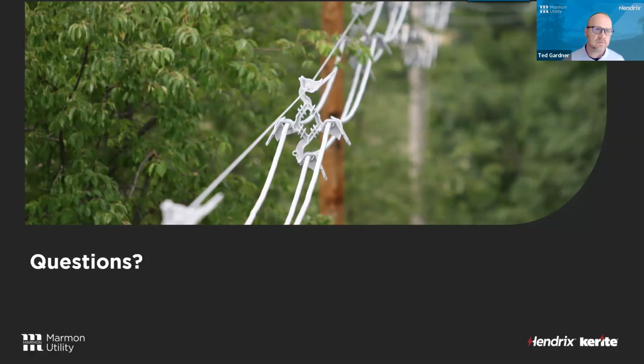We'll use anything from SAG 10. Most of our engineers these days are using PLS-CADD, and we can model that ice buildup. We've got a lot of pictures, I think some of them are here in my presentation, that show us during ice storms and bringing trees down on the spacer cable system, and it tends to perform really, really well there. That's what we typically see. I can't really speak to ADSS.